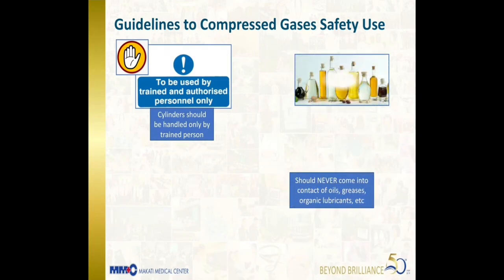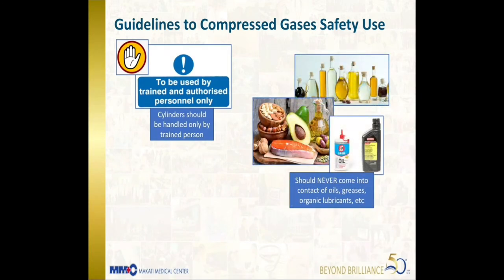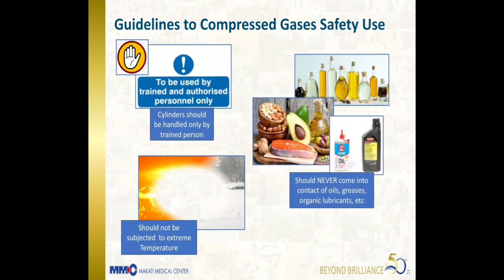Compressed gases should never come into contact with oils, greases, and other organic lubricants. Medical gas, especially compressed oxygen, will react violently to oil and greases, resulting in fire or explosion.